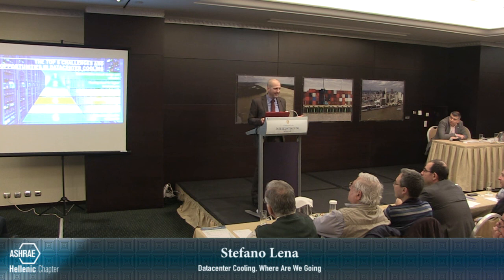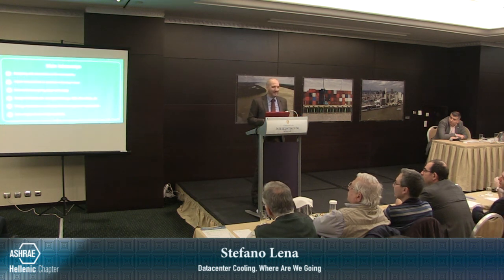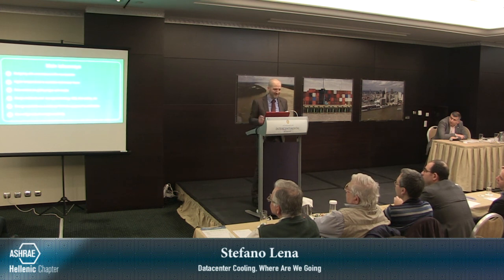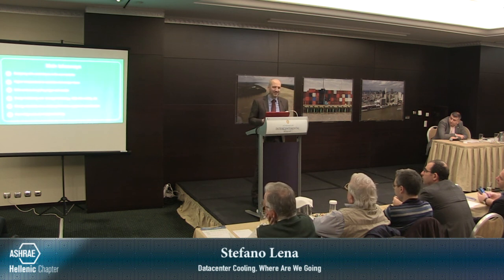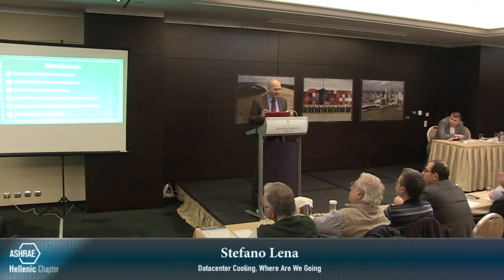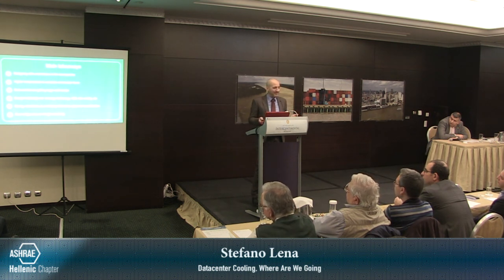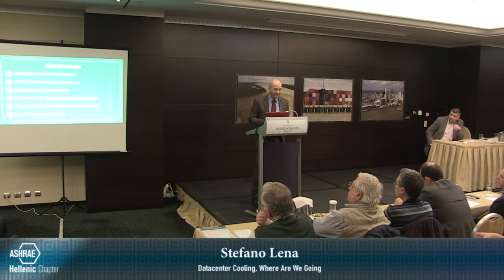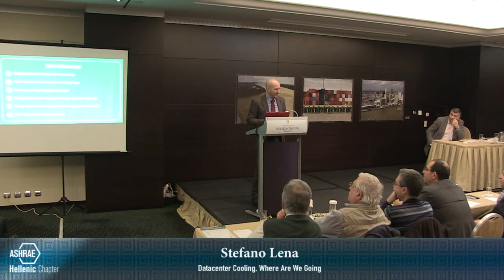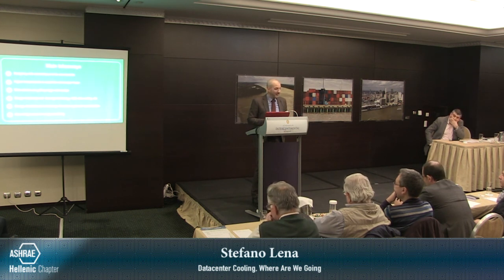Our takeaway for you is a guideline on how to face those challenges and how to try to win most of them. Design with economization as the baseline, and then adapt the trim part as small as possible. Use higher temperature to maximize the economization hours, and keep in mind that efficiency can be applied in different ways in big data centers and on the edge, and remember the scale effect. Design holistically using the circle and rely on prefabricated and pre-validated solutions from vendors. The energy standards are an opportunity to push the adoption of the most advanced technology in order to unlock efficiency. And the new refrigerant is not only greenwashing, it is an opportunity, because overall it is the best option to take care of our world. Thank you very much.